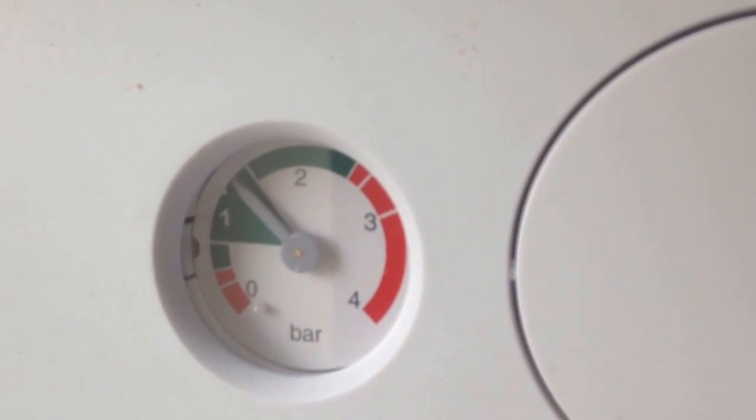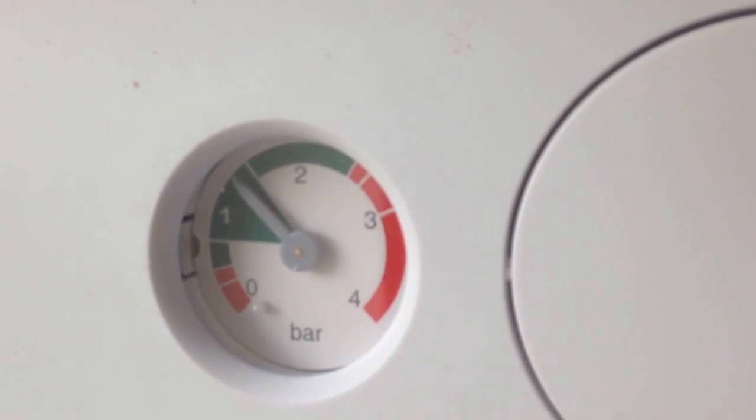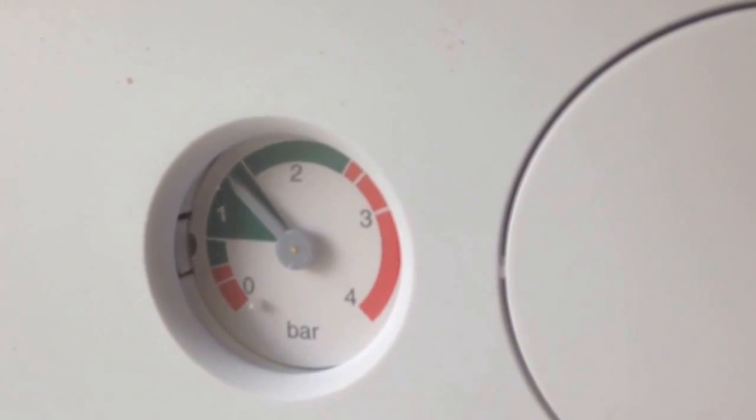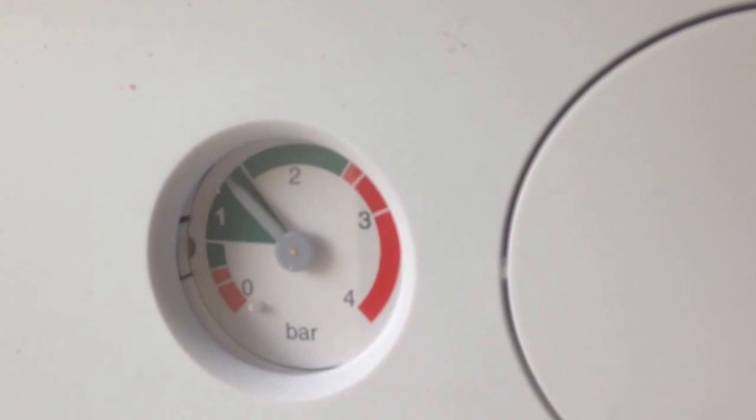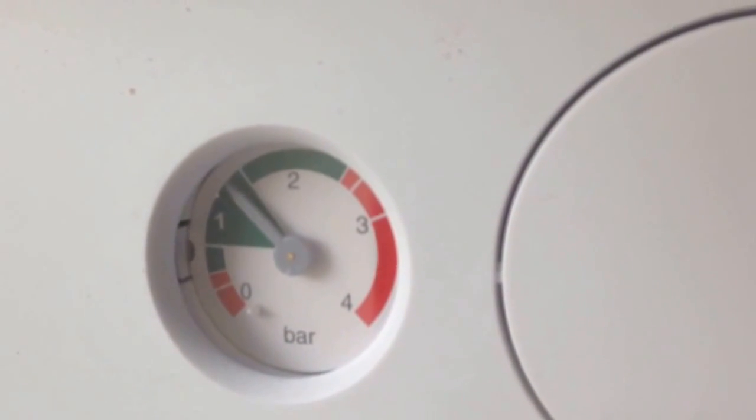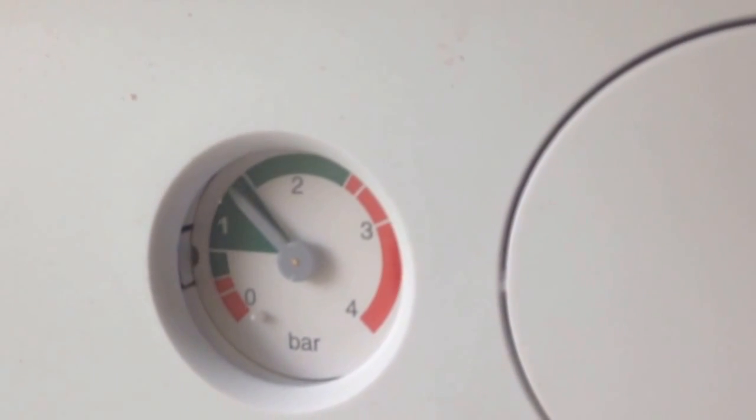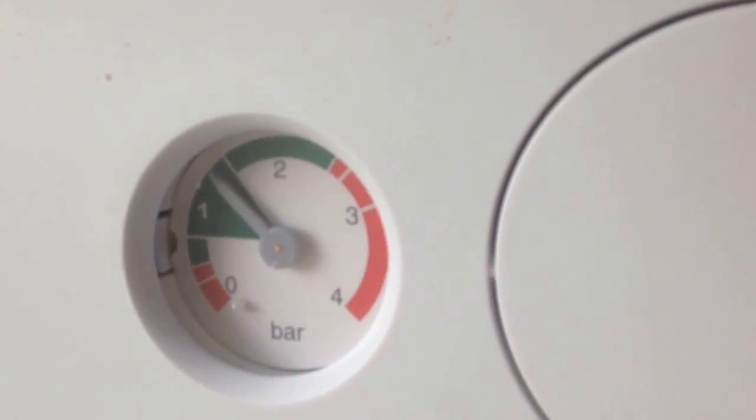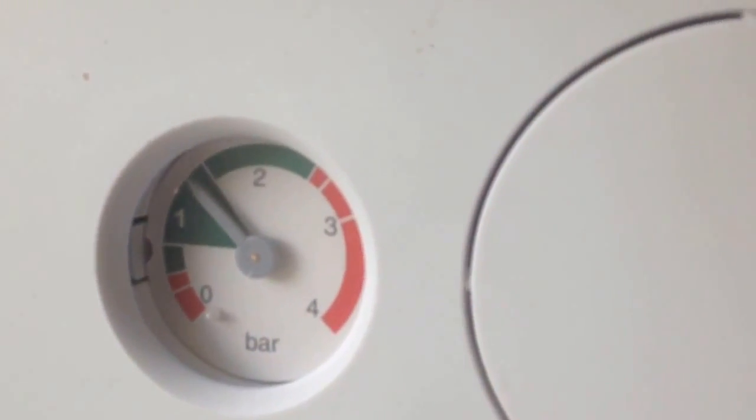Now one of the reasons why that pressure might have dropped: you might have a slight leak among the radiators. And also, if you've got the top of the radiator which is cold, then you've got to bleed the radiator to let the air out and then put the pressure back up, which I'll show you in a second.